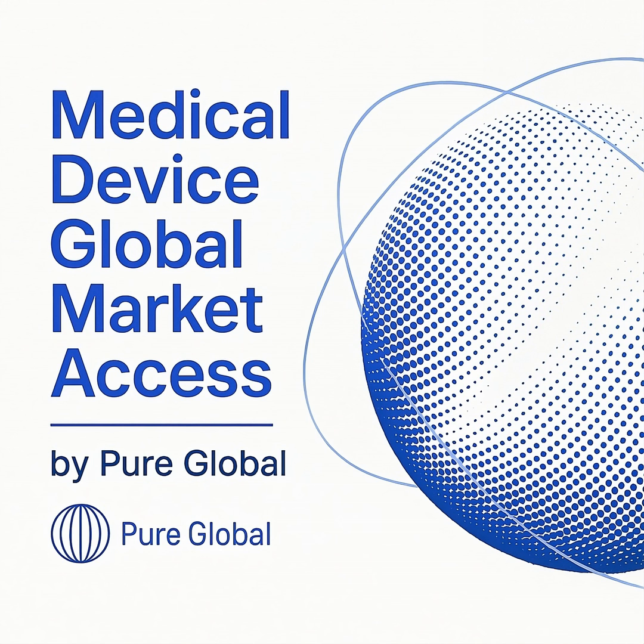The most profound change is the deep and comprehensive integration of risk management. It's no longer just about managing the risks of the investigational device itself. The standard now mandates applying the principles of ISO 14971, the risk management standard, to all stages of the clinical investigation process. This holistic approach, detailed in the new Annex H, means sponsors must identify, evaluate, and control risks associated with the trial's design, procedures, and data collection, ensuring a constant and documented benefit-risk analysis throughout the study's lifecycle.